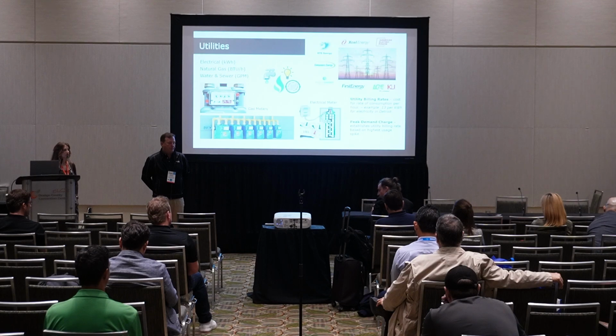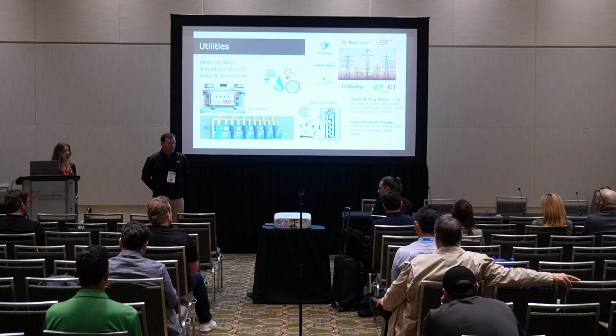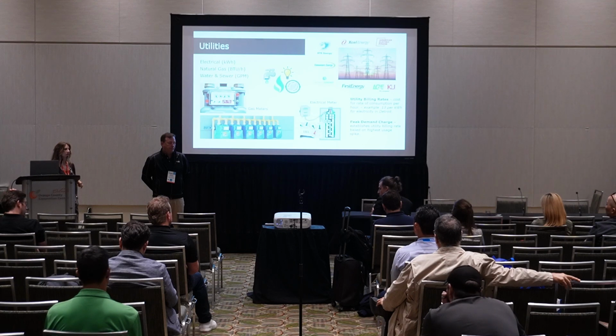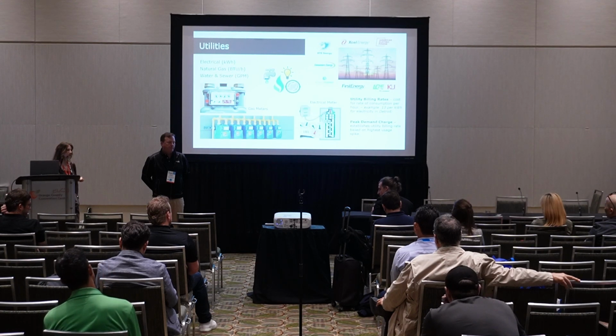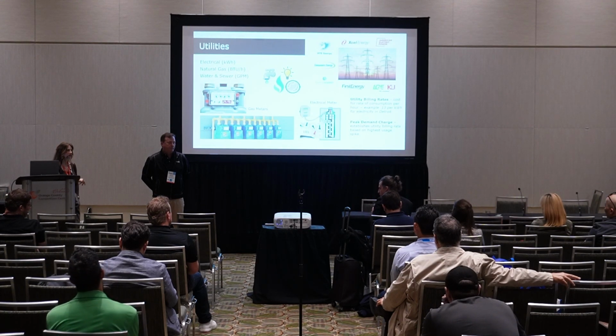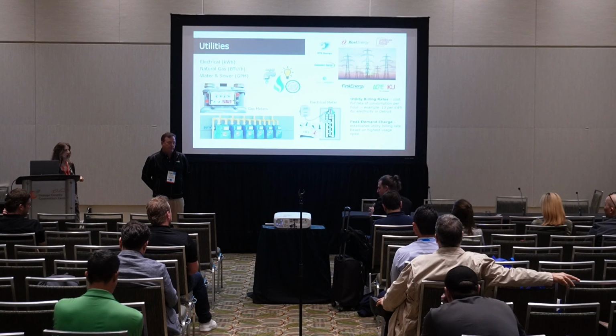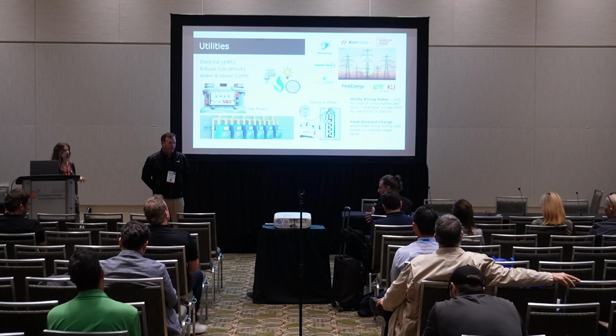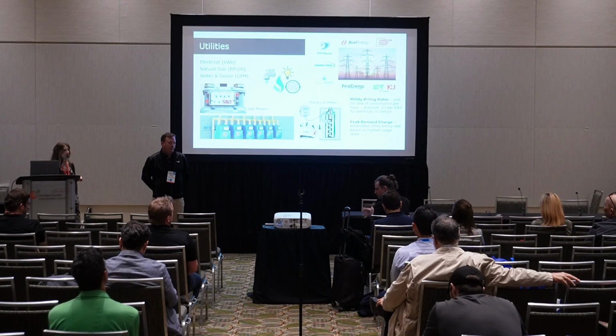You've got to be careful to select the right drive that's not going to adversely impact things, but if you're careful, you can choose the right devices and load shed them. I actually prefer that, I call it kind of like direct load shedding, where you're directly reducing the speed drives.